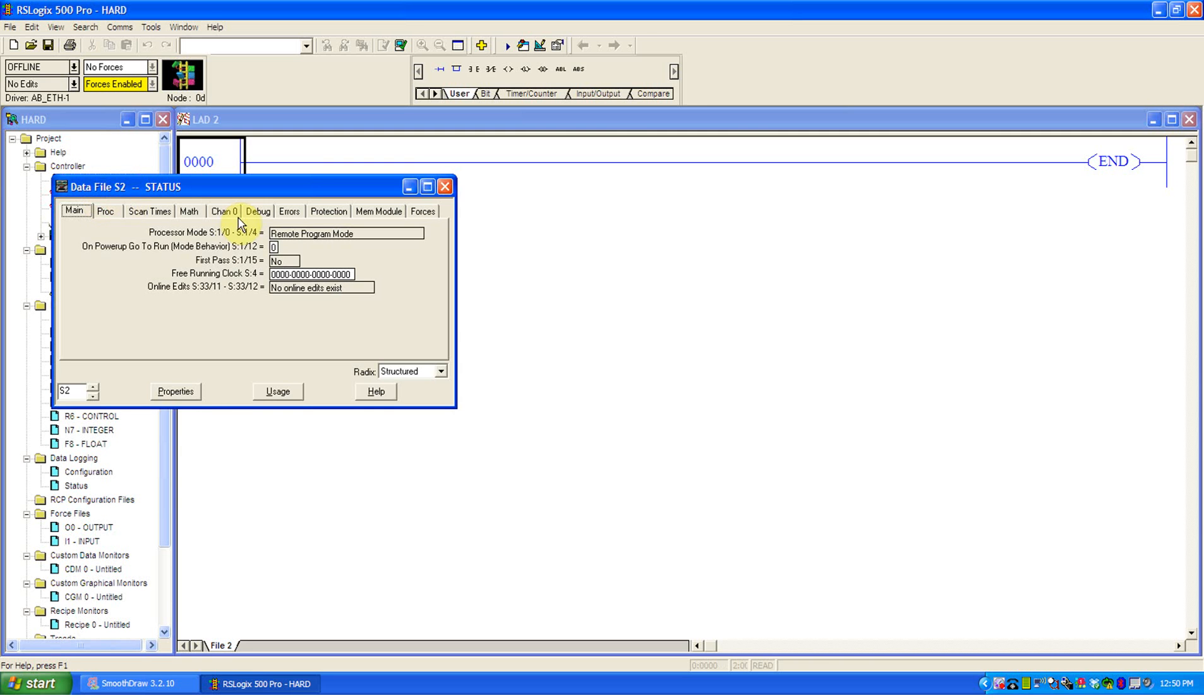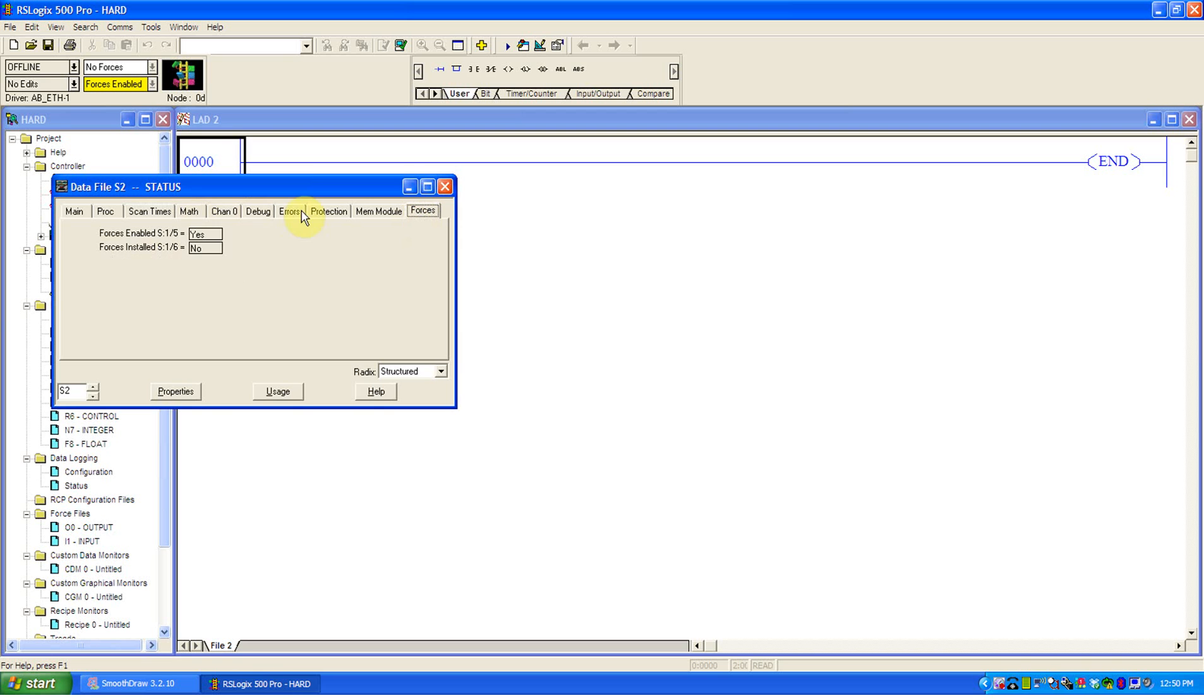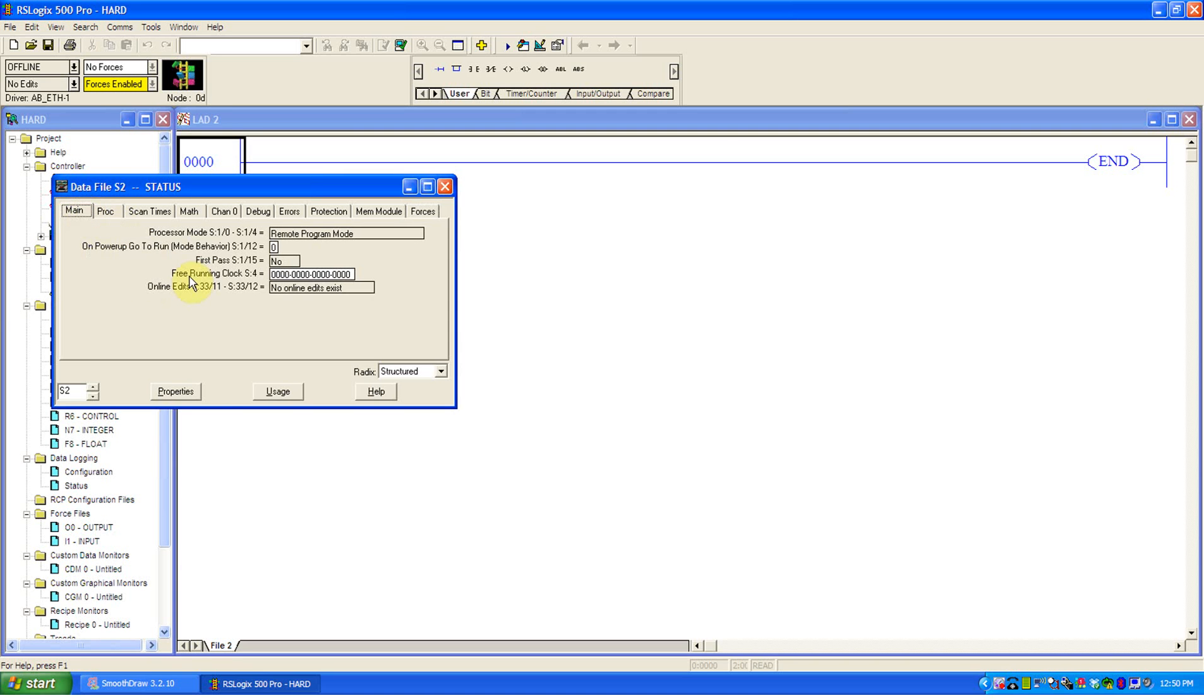If you go into status, this is where your errors and scan times, like you'll see how fast scans are happening. You'll get a watchdog timer if it's greater than 10 milliseconds. Errors and forces, if there's forces installed in the program. You can actually search those forces here. The reason I point this out is this is also where there's what's called the free running clock which is S4 colon, or S colon 4, whatever bit you're after.